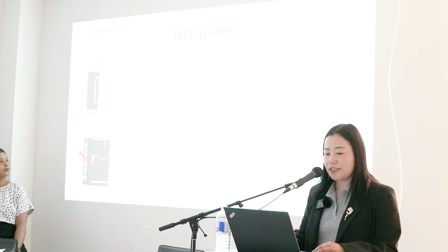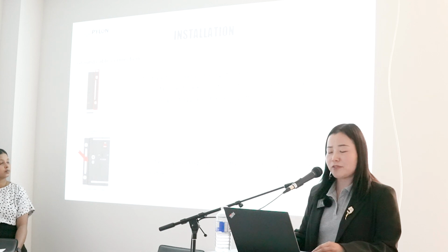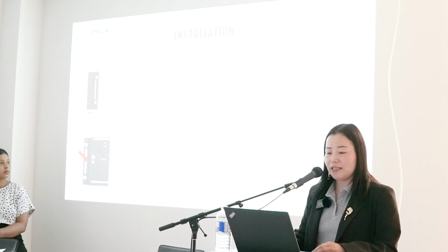So this is the ground cable connection. You have two options. The first one is based on metal directly touching between the module surface and the rack surface. But if using a painted rack, the corresponding place should have the paint removed. Second option, you can install a grounding cable to the grounding point of the module.